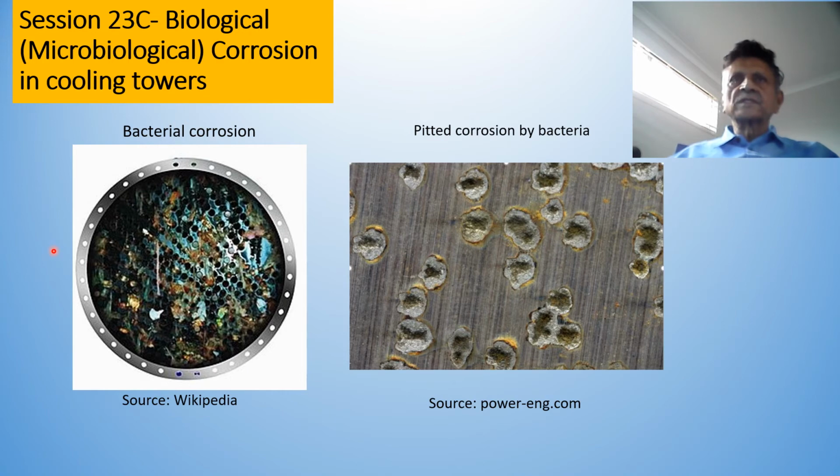This slide shows the metals with bacterial corrosion. This is an end pipe of a chiller, and if you notice, usually the solder joints, etc., can be attacked, which contain probably iron and other metals. And here, each of these pits indicate a colony of bacteria.